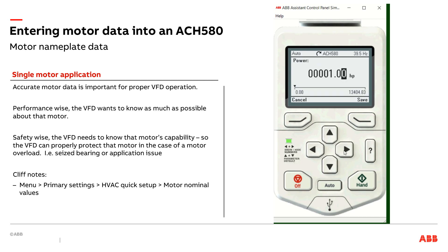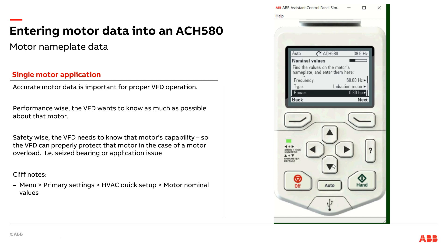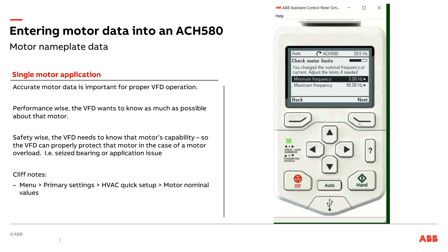By the way, it's a little guy — only 0.3 horsepower. I can put in the cosine, my power factor, if I want. It's not too critical for an HVAC drive in scalar mode. The other things at the end are not too critical either, so I can go ahead and hit next.